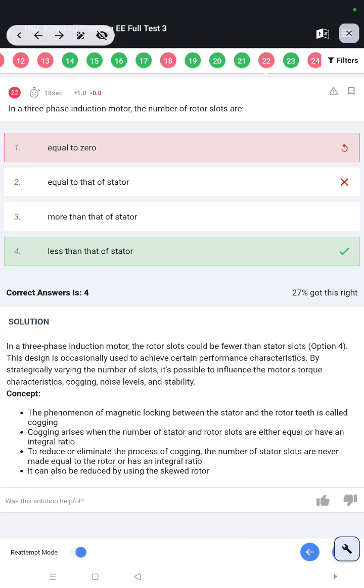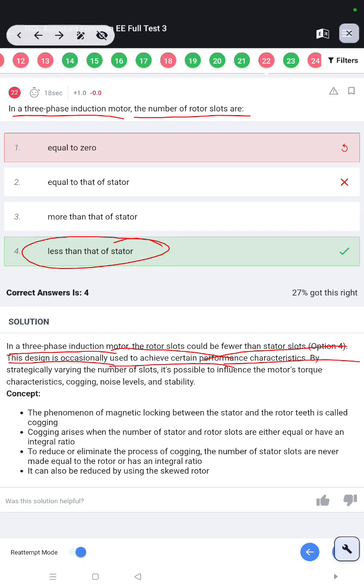In a three-phase induction motor, the number of rotor slots is less than that of the stator. In a three-phase induction motor, the rotor slots could be fewer than stator slots. This design is occasionally used to achieve certain performance characteristics by strategically varying the number of slots. It is possible to influence the motor's torque characteristics, cogging, noise levels, and stability.